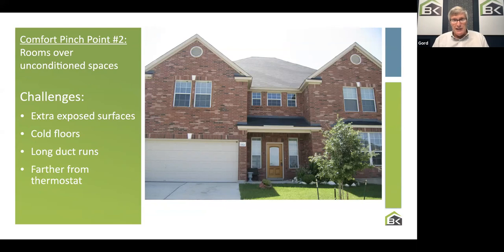Of course, the challenge here specifically is you have more exposed surfaces. You have not only the normal ceiling and maybe one exterior wall, maybe two exterior walls - here you have three exterior walls the way this one juts out, plus the floor. You've added to the total heat loss and total heat gain of this room. At least there aren't huge windows, but we still have windows to think about.